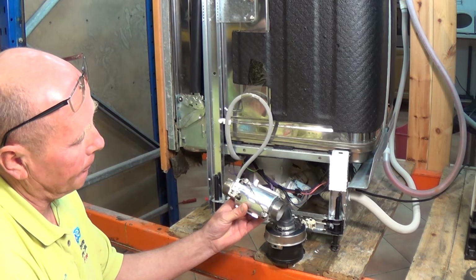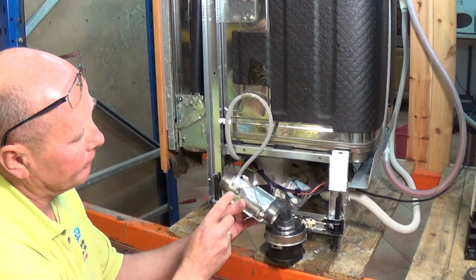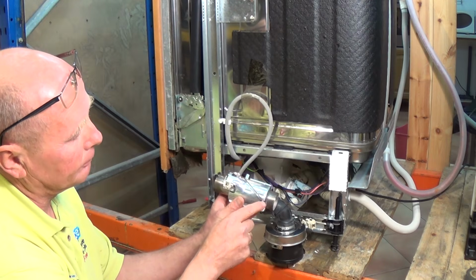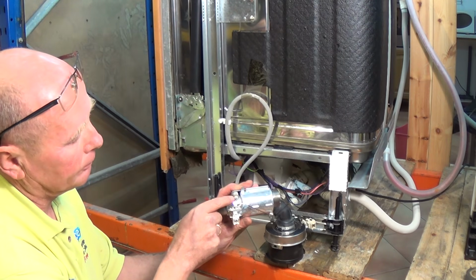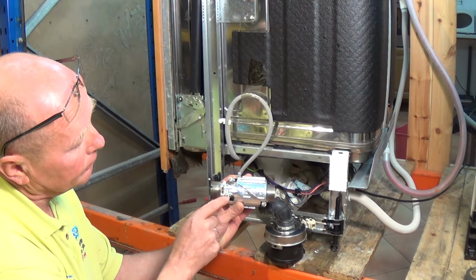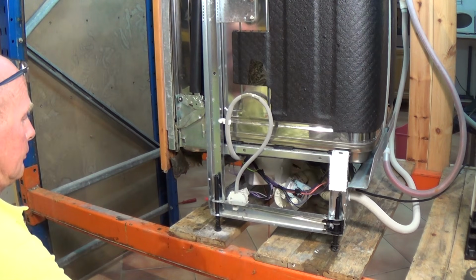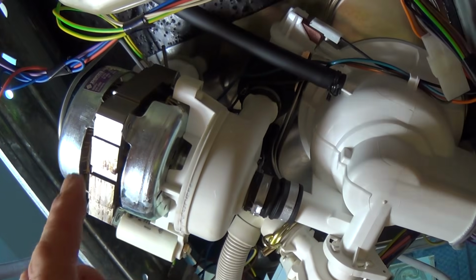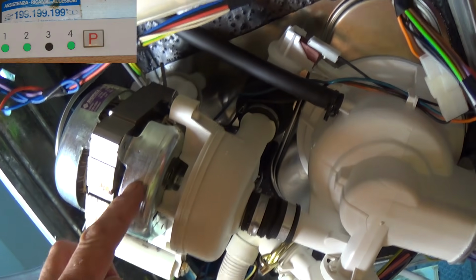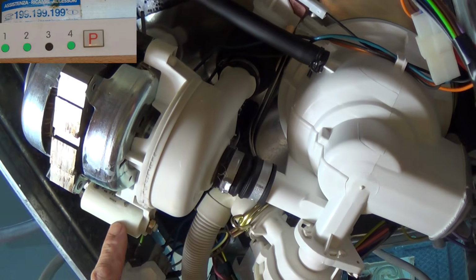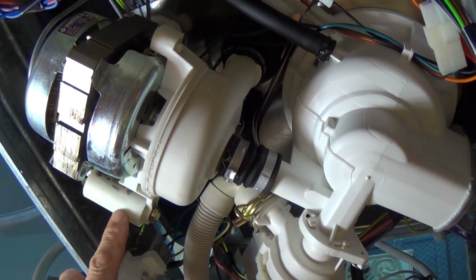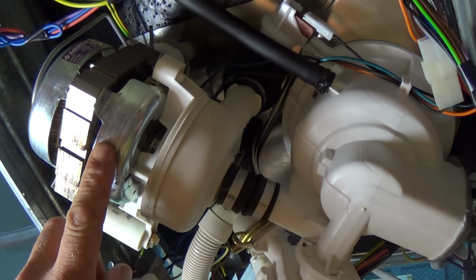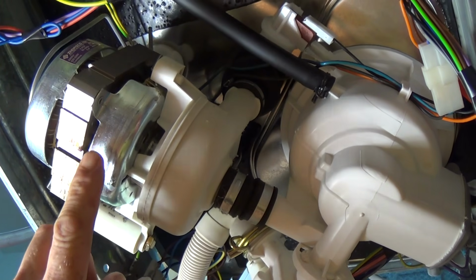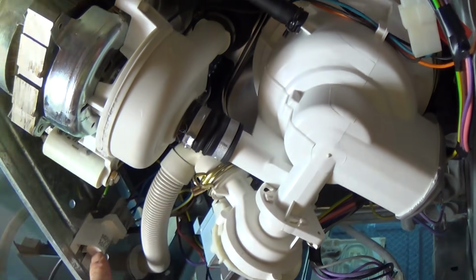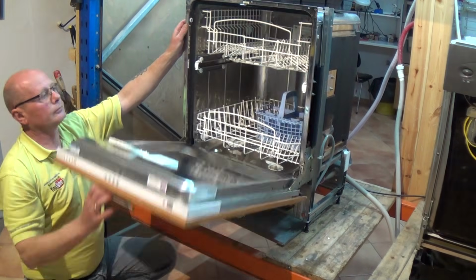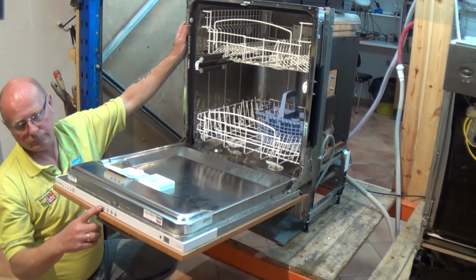And this one is what we call an inline heater, and this fits between the motor and one of the pipe intakes. Again, there's two small thermostats. These can't be changed. It comes as a complete heater unit. Now F11 is 1, 2 and 4 will be flashing, and this is motor related fault. It could be a capacitor, it could be the seal has collapsed on the impeller and rusted one of the bearings and the motor hasn't got enough power, or it's a motor failure completely.